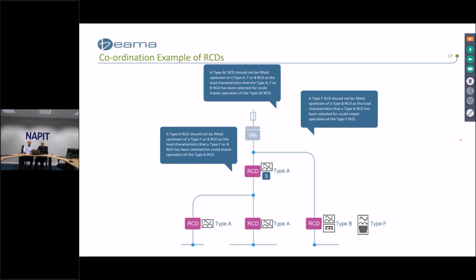For instance, a type A RCD can only be downstream of a type A, a type F, or a type B. So if we took the middle section of this graphic that we have, where we've got type A with a downstream of another type A, you could not fit, or should not fit, a type B or a type F at the downstream position, because any fault currents that the downstream type F or type B detects could influence or even stop the upstream type A from working. It could have a significant effect on the performance of the upstream type A.